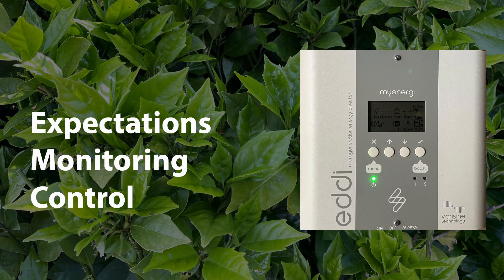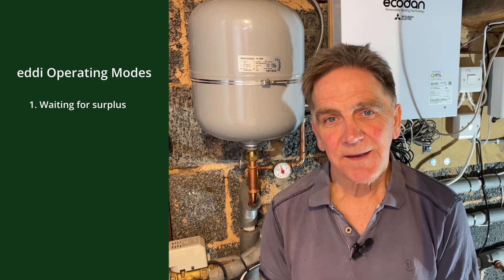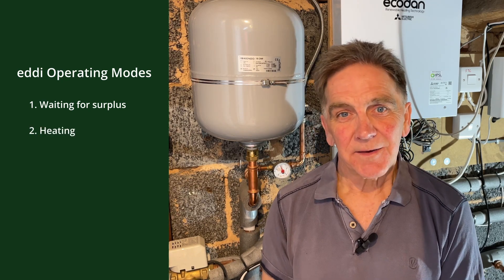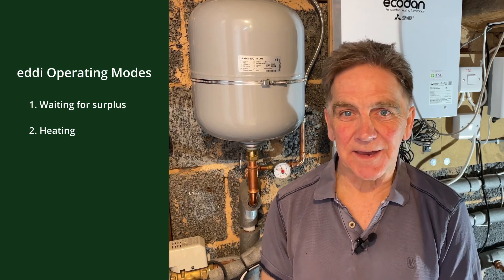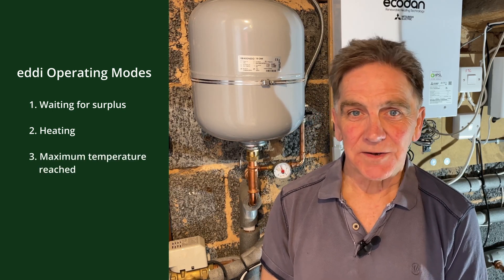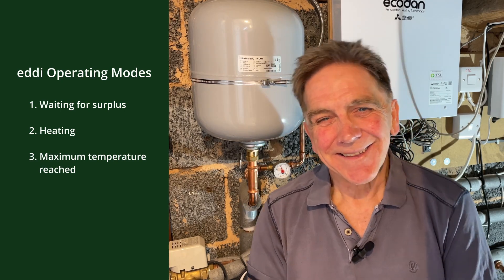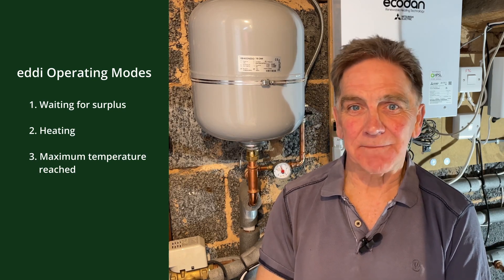So hot water from surplus solar energy is what to expect from your eddi, but how do you monitor what it's doing? The eddi has three principal operating modes. The first is waiting for surplus, which means that if anything is being generated by your solar PV array, it's all being used by the house. The second mode is heating — surplus energy is being directed to the eddi and the water is heating up. The third mode is maximum temperature reached, which means the water is up to temperature and any surplus generated is being sent back to the grid. The operating mode is displayed on the screen of the eddi.